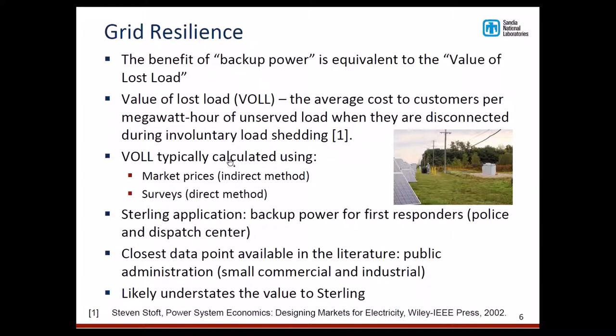Typically, you calculate value of lost load to look at this benefit, and there are two different ways to come up with that number. One is market prices, and the other is surveys, and surveys are probably more prevalent. We relied on some data from a Lawrence Berkeley report that looked at public administration, small commercial and industrial, but it came out to about $40,000 per year for one big outage.